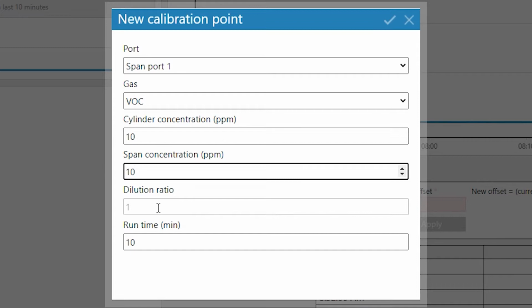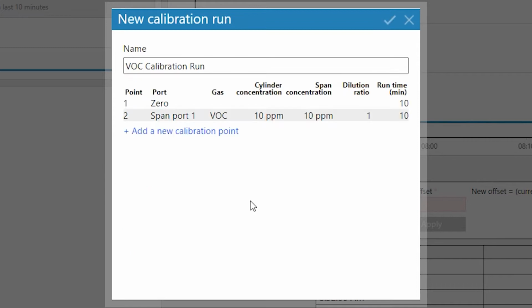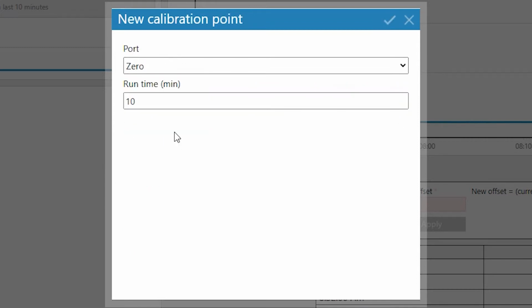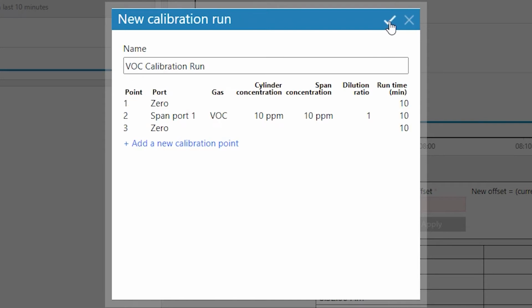So that's changed there. And then finally, we just added a third calibration point for a full calibration, which is another 0. So what we're going to be doing is giving zero air to the module. Then we're going to be giving our VOC gas isobutylene at the concentration of 10 ppm into our module, and then we're going to be giving zero air again. So this is our calibration run for today. So I'll just select that.